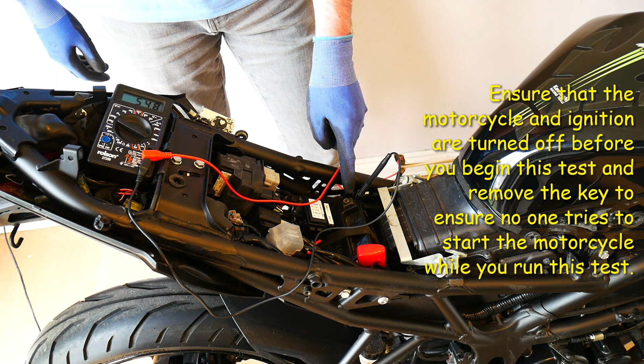So what this is measuring on the multimeter here, I have it set to measure milliamps. So it's measuring current. It's called the leakage current. Now I'm measuring direct current. I set it initially to the 5 amps range, and I measured to see what amperage was coming from the battery to the lead. It indicated close to 0, so let me just put it back to 0 here briefly. So as you can see, it's just measuring 0.00.